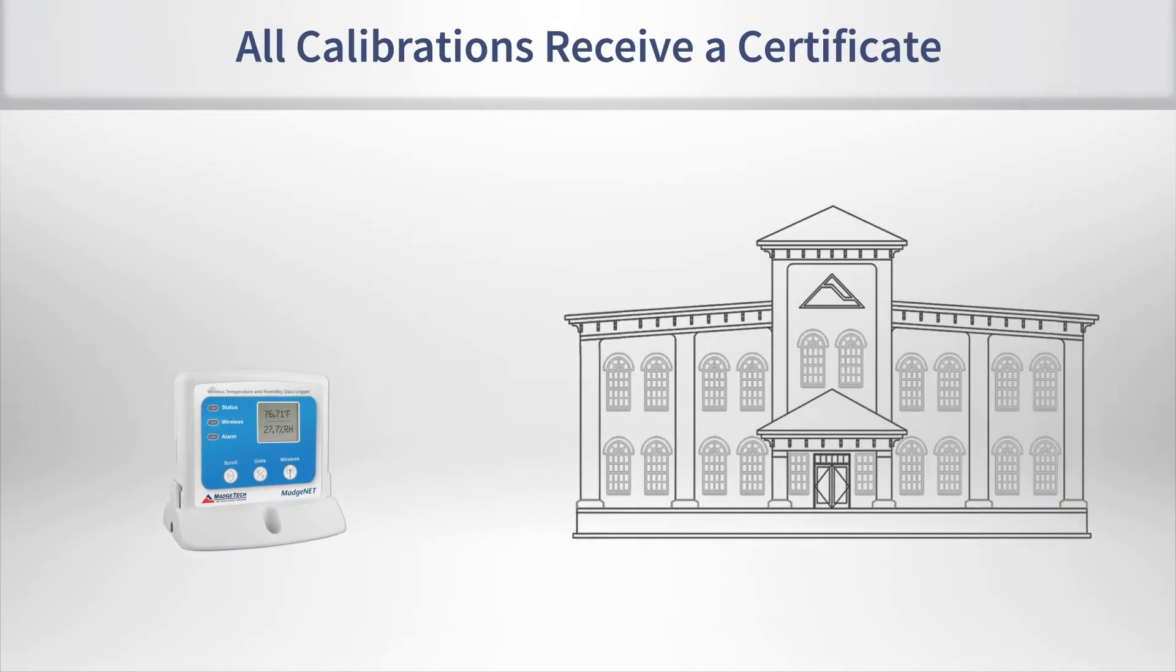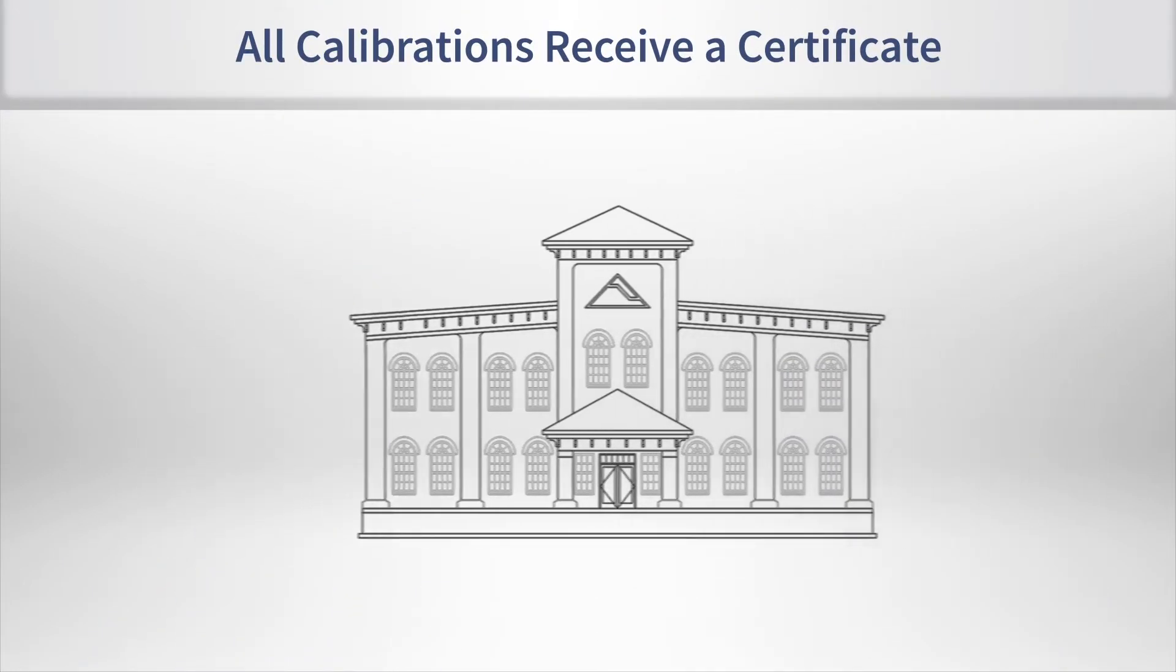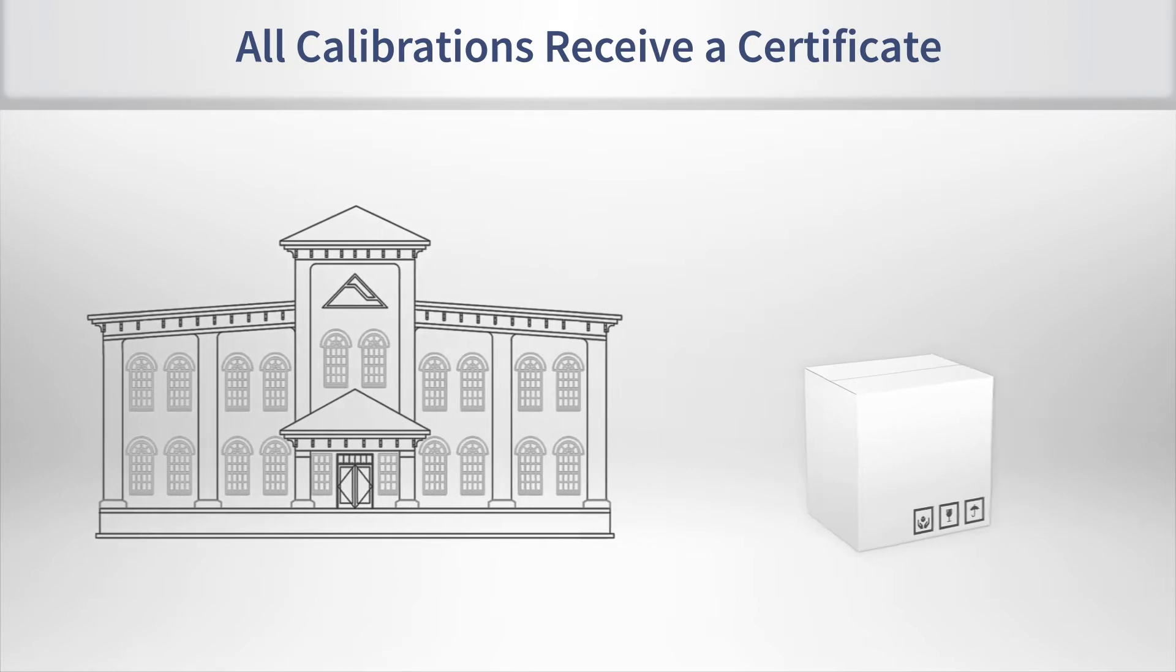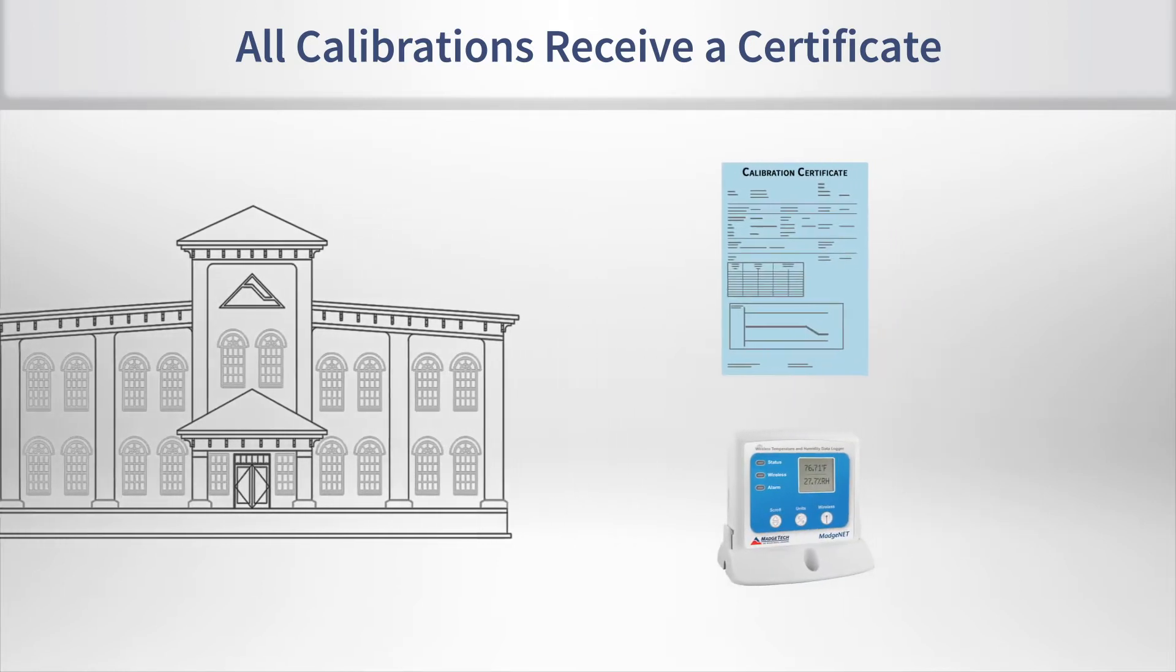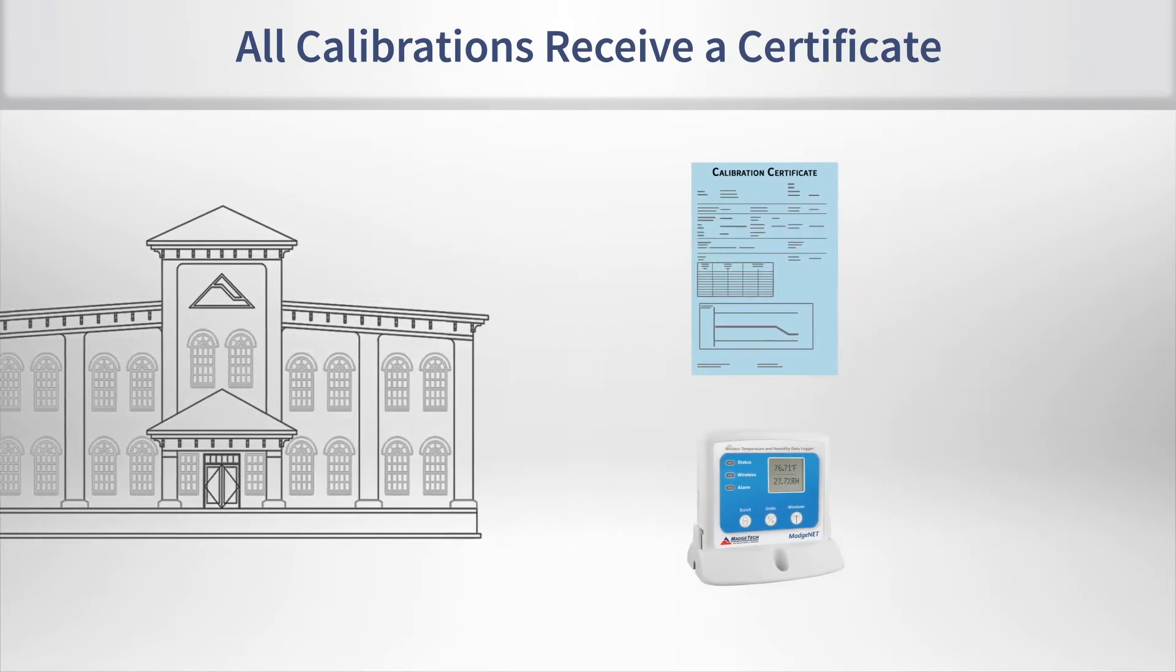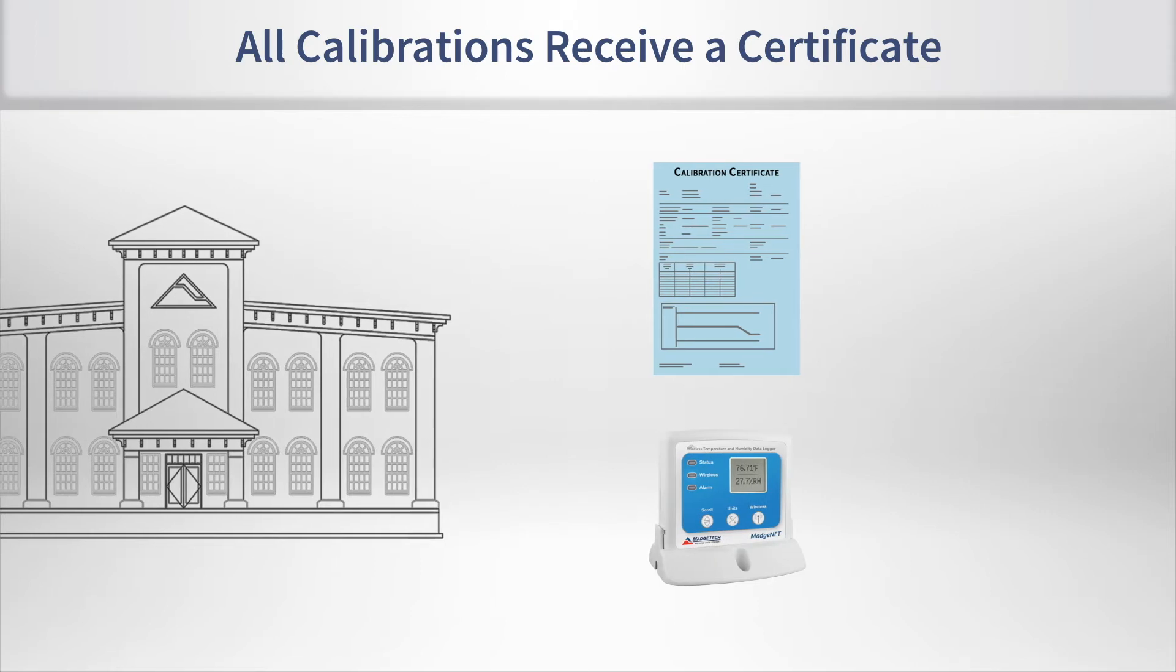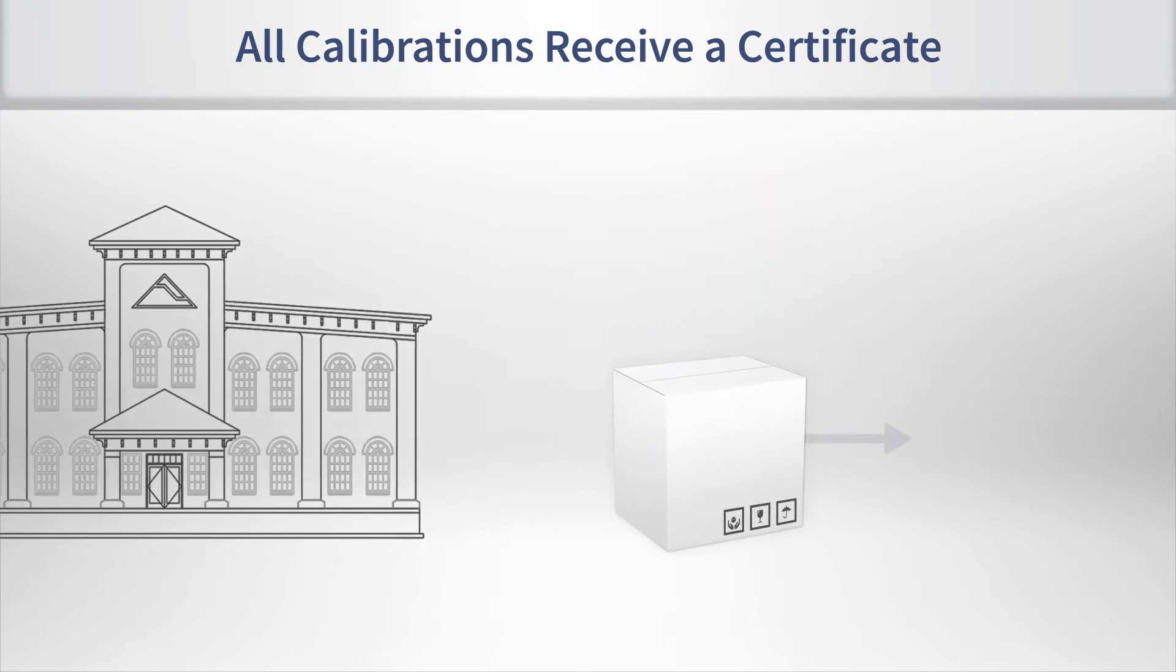Any logger sent into the MadgeTech facility for calibration, even for non-accredited calibration, will still receive a calibration certificate documenting as-found and as-left data as well as listing our NIST-traceable reference equipment that was used in any process.